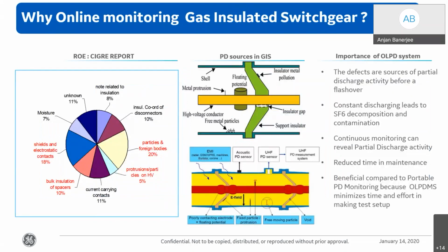When it comes to gas insulated switchgear, I would like to share a statistic available in one of the CIGRE publications. This publication documents the root causes of GIS failure, and we find that moving particles, protrusions on the HV conductor, and voids in the insulator are the sources of partial discharge within GIS before an electrical flashover occurs. Because of this discharge activity within GIS, there is continuous contamination and decomposition of SF6.